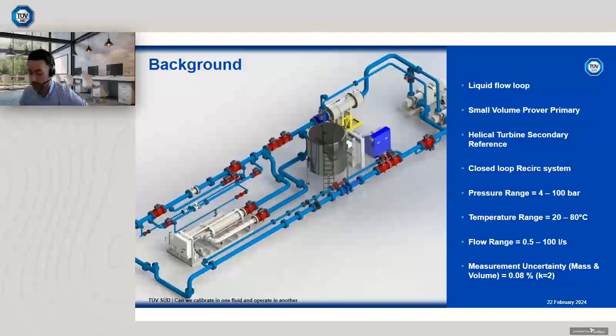So we completed a joint industry project, a JIP, with 14 sponsors, looking at 3 different Coriolis manufacturers of 2 meter sizes, so nominally 3-inch and 4-inch Coriolis meters from 3 of the main manufacturers. And we tested them at various pressures and also temperatures, and we discovered there was a clear temperature and pressure and also a viscosity/Reynolds number effect for Coriolis meters. However, there was a lack of traceable flow facilities that could operate at these elevated temperatures and pressures, certainly with a great deal of stability and a relatively low uncertainty.